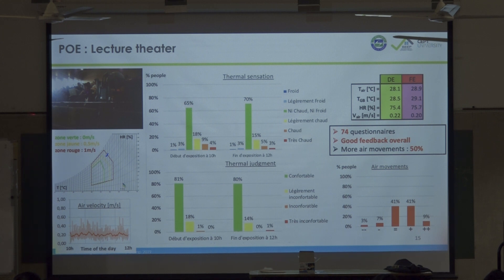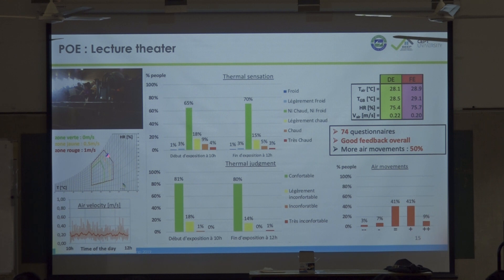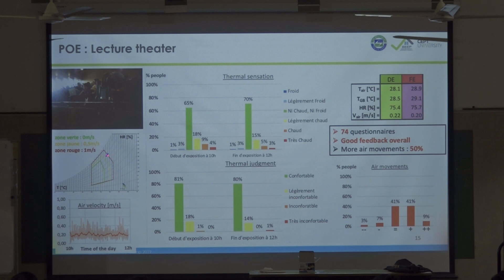We did a post-occupancy evaluation — measuring black globe temperature, air velocity, air temperature, and humidity. The survey was conducted in February, which is summer and hot. The conditions during the survey were close to the larger Givoni zones, meaning in theory we need one meter per second to feel comfortable.